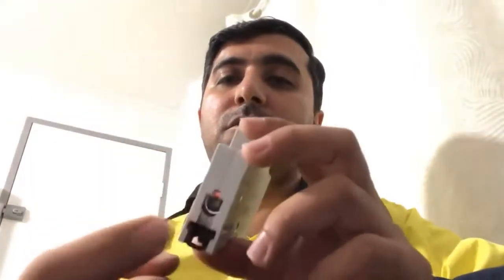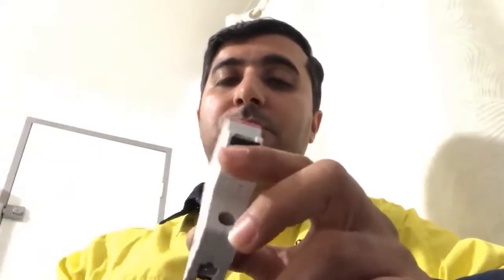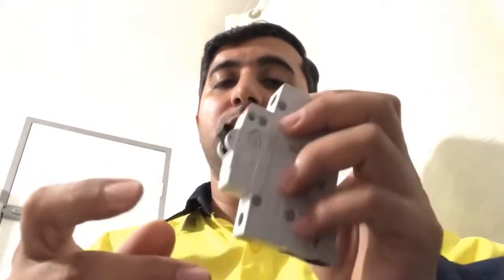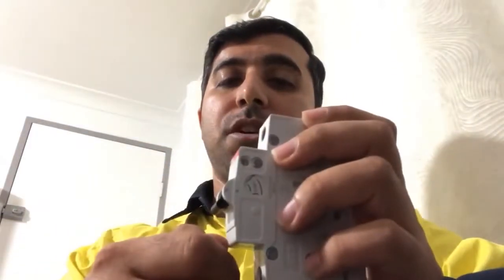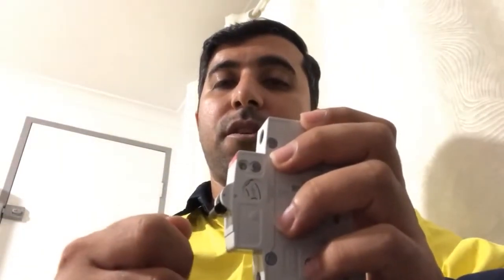One comes from the grid supply connection. The other one goes to the load, or your appliances, or the power point or the light. So what it does is that if there is any kind of overload, whether it's excessive overload or a small overload, it can be detected by the circuit breaker, and the circuit will trip. It is an indication that there is a fault in your appliances or somewhere else, or even inside the wiring. So when the problem has been resolved, you can trip it back on. There is less chance of messing up with that one, because there is nothing you can do about anything inside the circuit breaker.